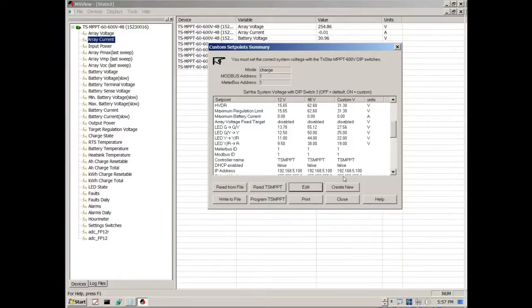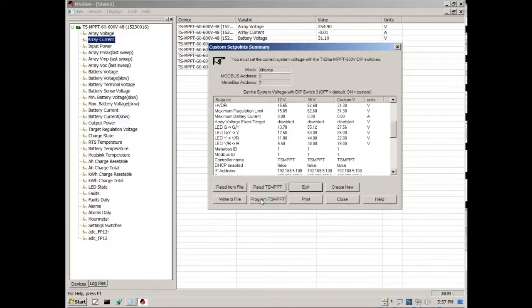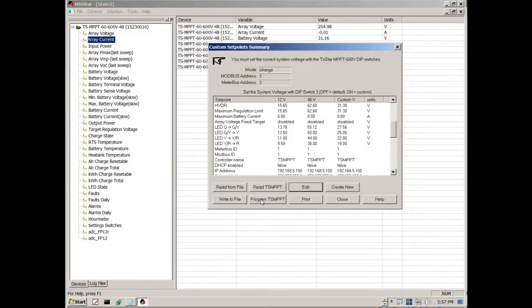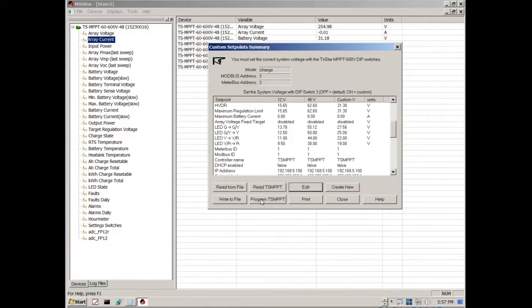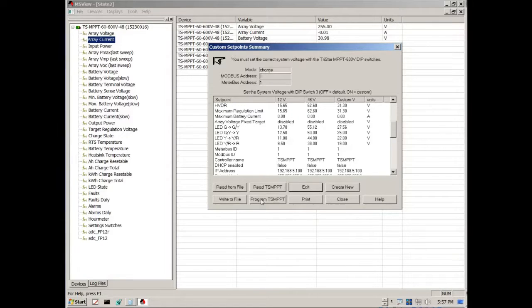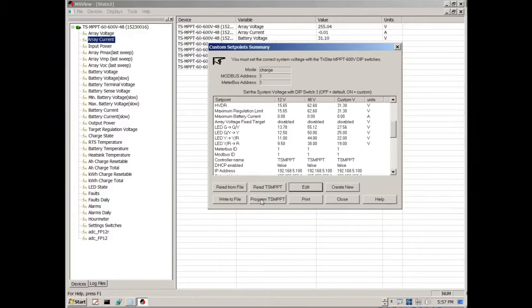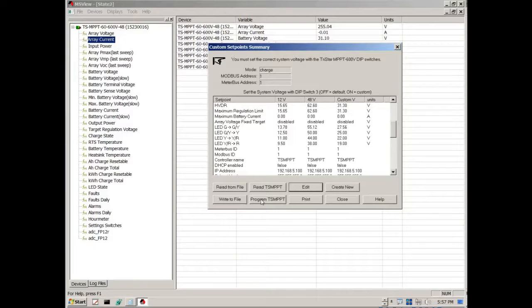And once that it's done, then you just simply click this button and it will send this information. It will program the charge controller. And the only thing that you have to do at that point is just shut down the charge controller. Just turn off the battery disconnect switch, the battery breaker, and then turn it back on. And that will put the new variables in effect. And that's it.